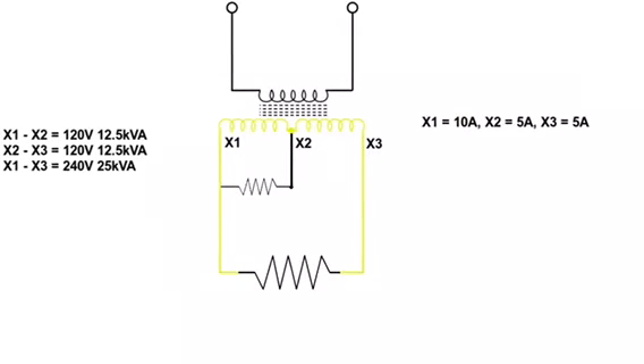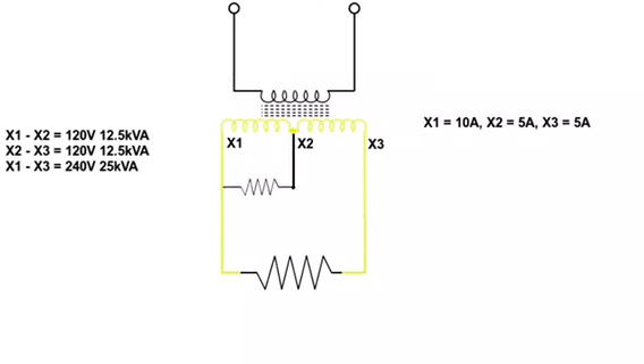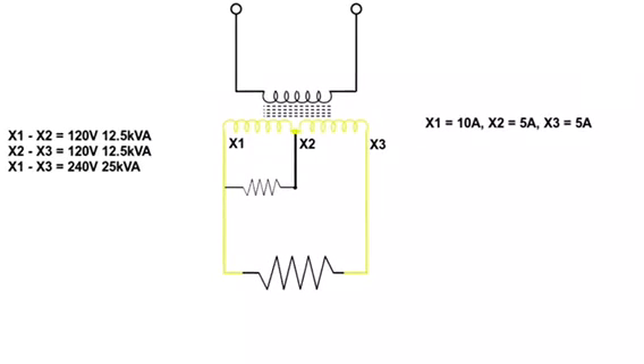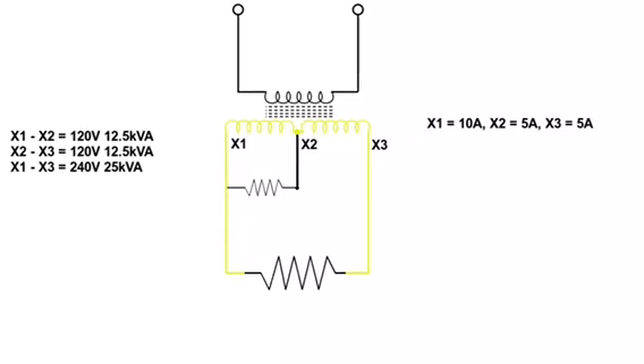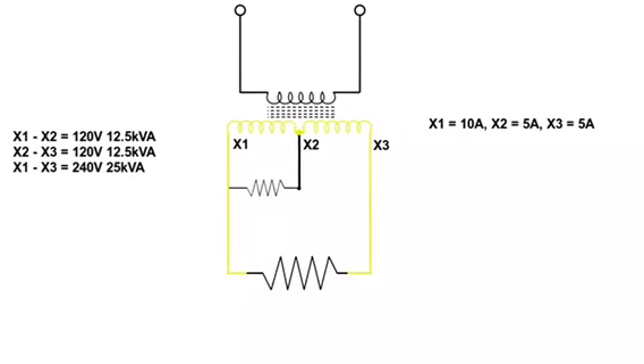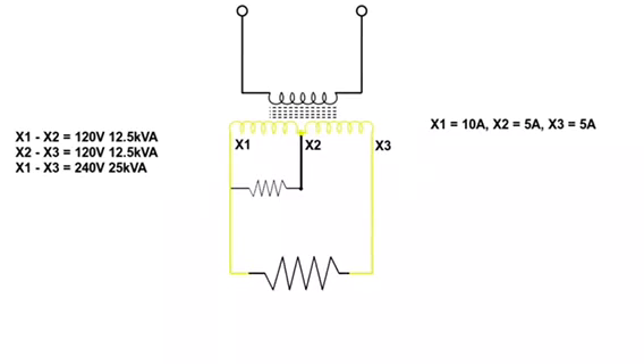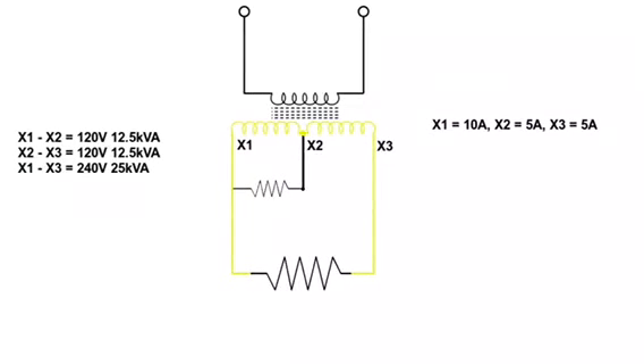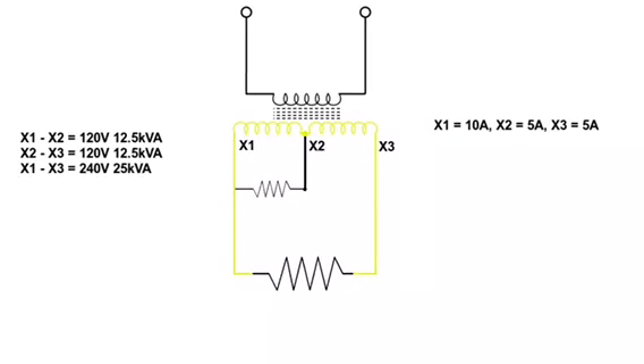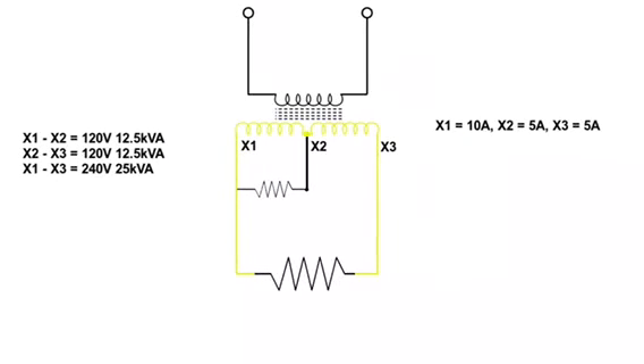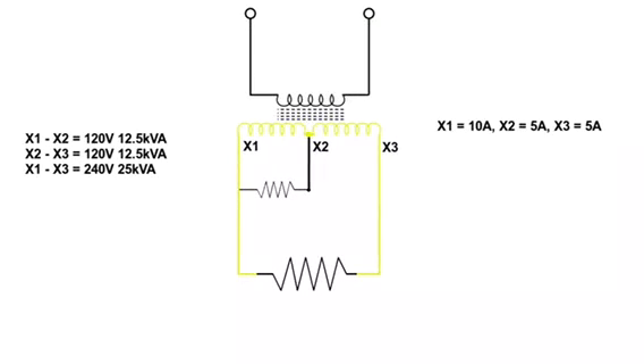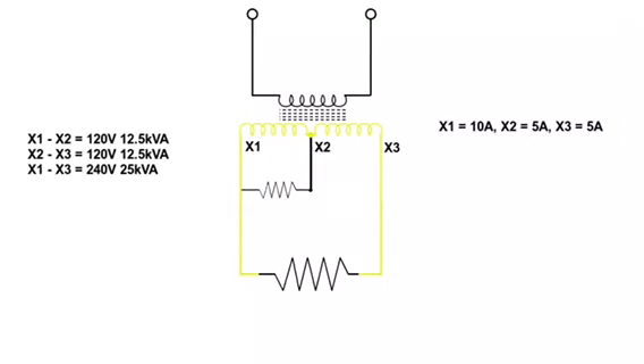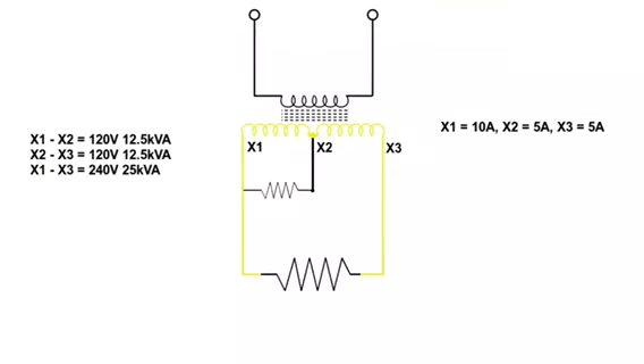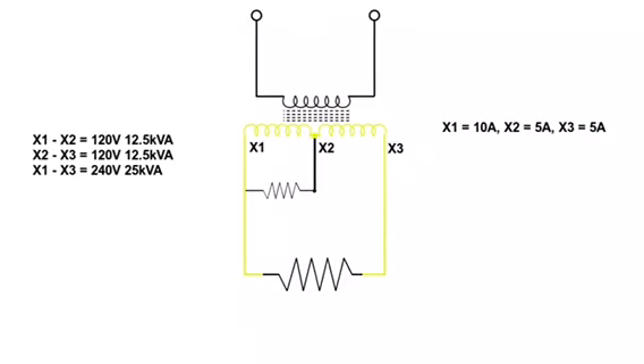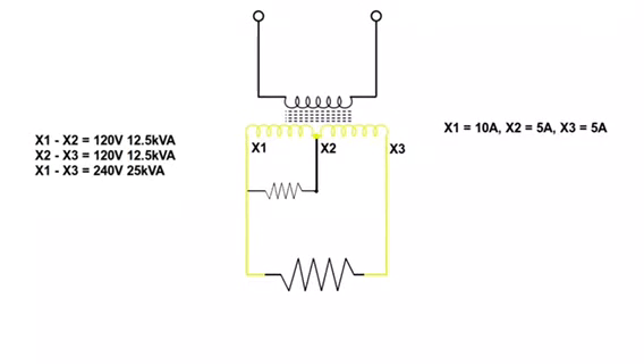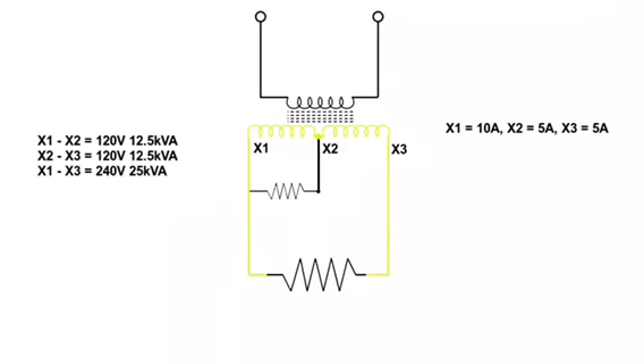Now I've added one of the 120 volt loads back. This is very common for what you'll see in a house. The 240 volt load running across X1 to X3 could be a water heater that's running. The 120 volt load in between X1 and X2 could be the light in your bedroom that's running. So right now, we have two things going on. The 120 volt load between X1 and X2 is placing a 5 amp load on that coil of the transformer. The 240 volt load running in between X1 and X3 is placing a 5 amp load on each half of the transformer.